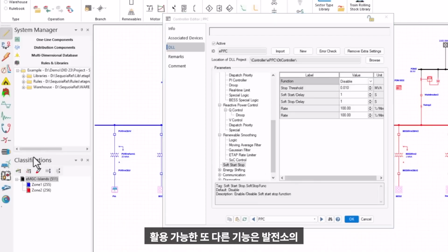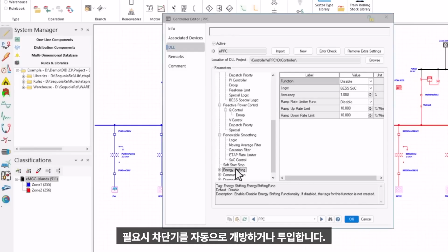Another available function is soft start and soft stop of the plant. This functionality provides a smooth startup and shutdown sequence based on commands from the operator, typically issued through the HMI. It can also automatically open or close breakers as needed, depending on the plant configuration and the settings selected by the operator.